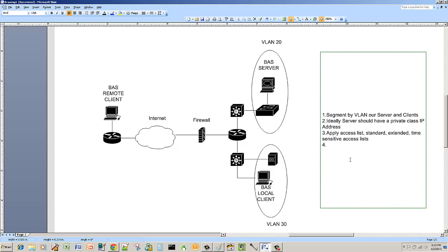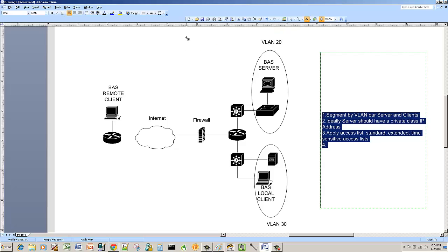Alright, number 4. So port forwarding and blocking. Big thing that people can do is they can bypass traffic by going through open ports. So for example, if you were to do a netstat in your command prompt, you would see what ports are open. Now typically a BAS system is going to talk ports 80, 443, so it's important you know some of the core ports.